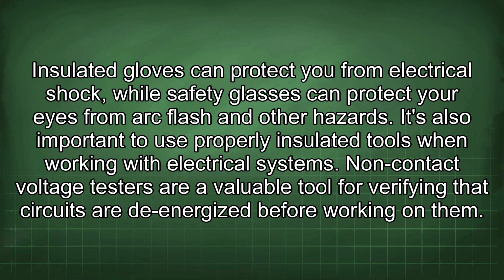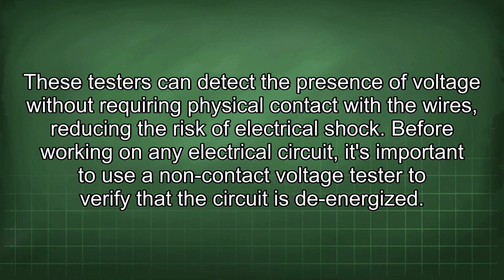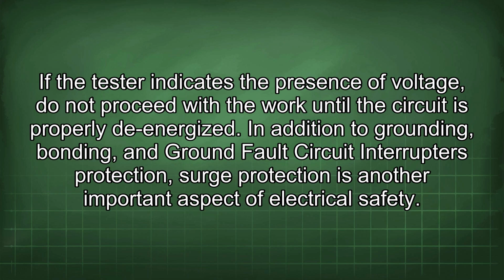Non-contact voltage testers are a valuable tool for verifying that circuits are de-energized before working on them. These testers can detect the presence of voltage without requiring physical contact with the wires, reducing the risk of electrical shock. Before working on any electrical circuit, it's important to use a non-contact voltage tester to verify that the circuit is de-energized. If the tester indicates the presence of voltage, do not proceed with the work until the circuit is properly de-energized.